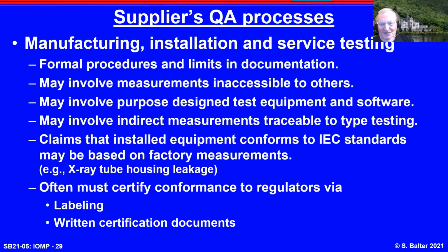The manufacturers have an elaborate QA process because they have to maintain the chain of accountability. So when they manufacture, they use formal procedures. They use a lot of measurements that nobody else can do, including their own people, once the equipment leaves the factory. They use very specially designed test equipment and software. Again, this is generally not portable, so it's only seen in the engineering lab and perhaps in the production line. They may do indirect measurements in production or in installation based on type testing and risk management. This is essentially a form of constancy testing, and we'll say more about constancy testing in a minute.